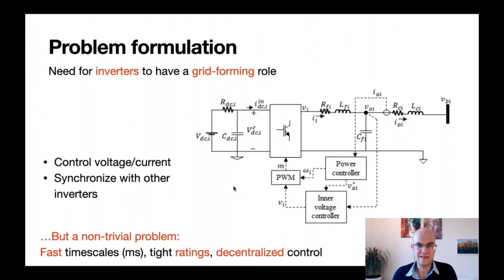Here we have a comparison of control implementation in conventional power systems and in converter-based microgrids. In conventional power systems, synchronous machines provide frequency and voltage regulation, and converters use phase lock loops to synchronize to the grid. On the other hand, in a converter-based grid, frequency and voltage regulation is provided by the converters.